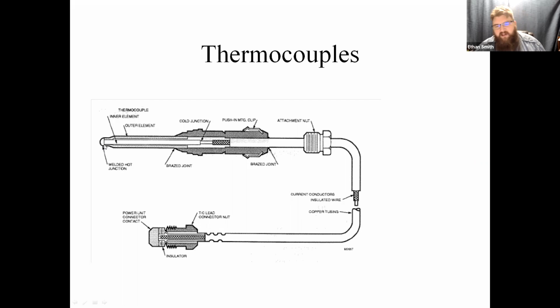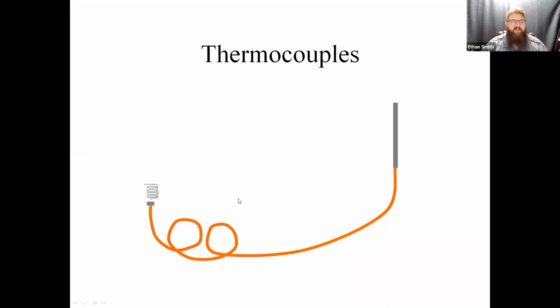The fun thing about dissimilar metals is that anytime you heat two pieces of metal that are joined together, they will generate a small amount of electricity. So that's what a thermocouple is. It's just a little micro generator. It's a thermally activated generator. We put these little thermocouples into the flame right at the tip, which is where we want that flame to be. And we heat that little thermocouple up until it generates enough electricity to hold the pilot solenoid on a gas valve open.